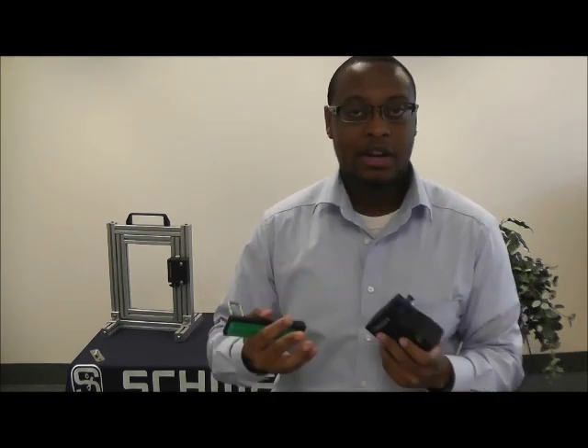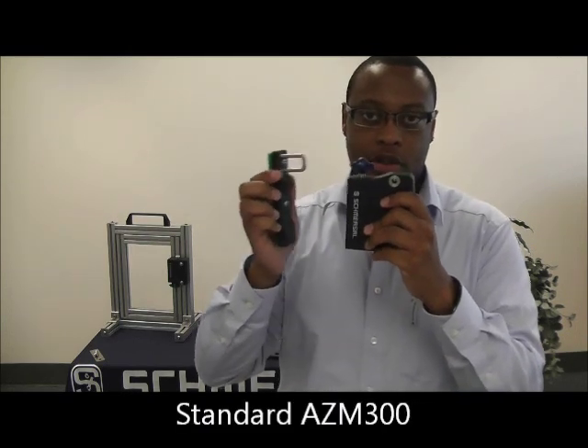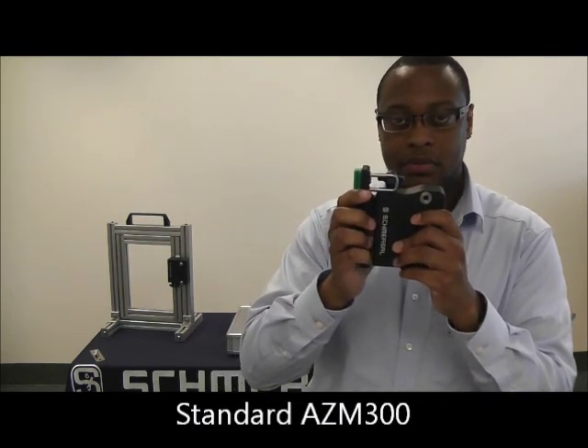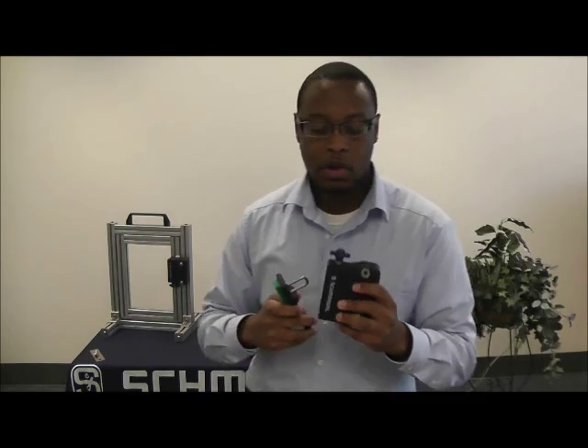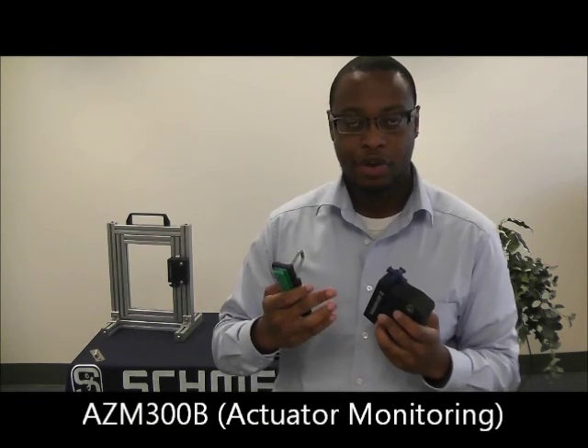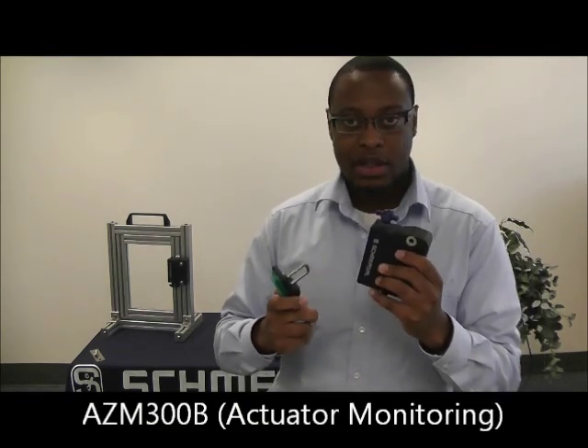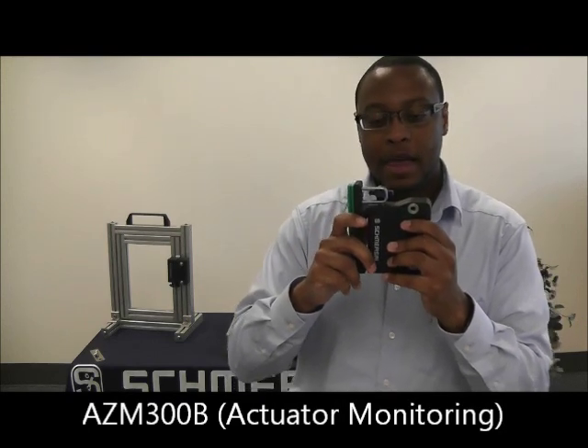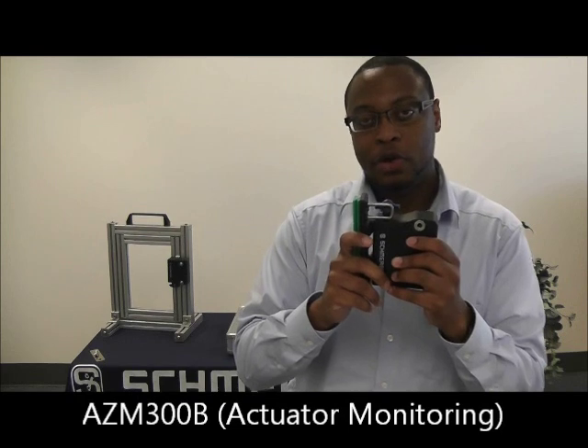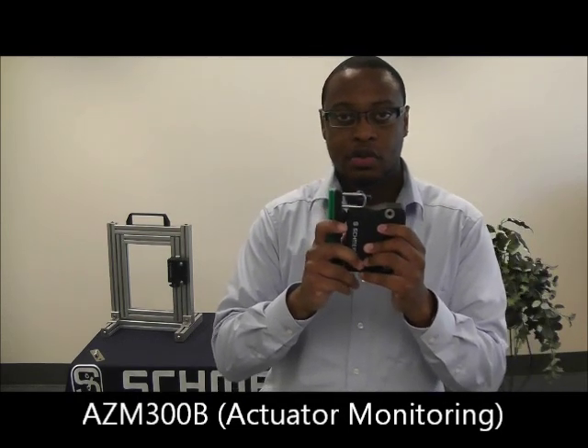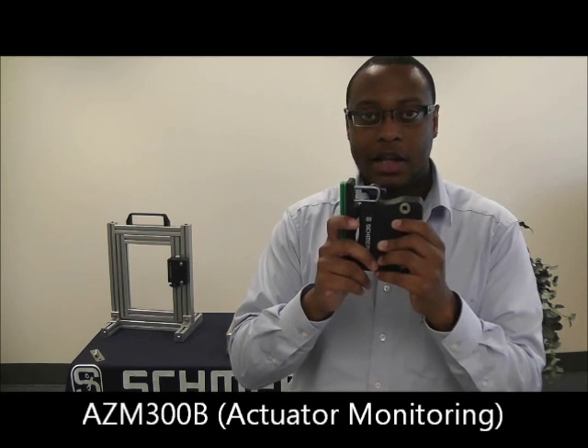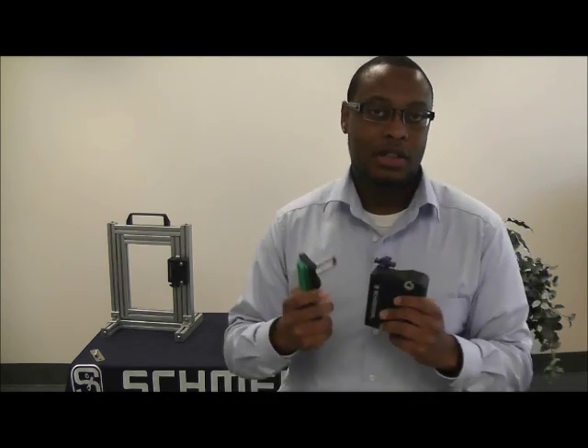Some of the options for the AZM300 include the standard version where the AZM300 is looking for the door to be closed and locked signal before you get your safety outputs, and we offer that with the power to lock and the power to unlock. We also have the B variant, with the AZM300B, where the AZM300 is looking for the door to be closed and that it can be locked, so it's not looking for the lock signal before you have your safety outputs. As long as the door is closed and there aren't any faults and the lock signal can be delivered, you will have 24 volts delivered at your output, and that's more for the process industry.